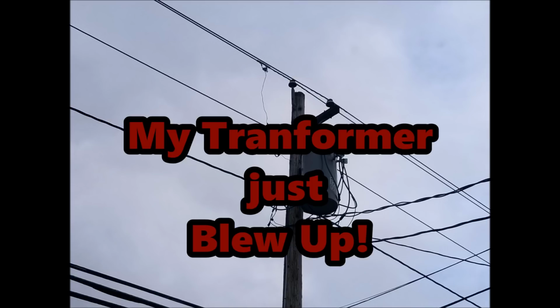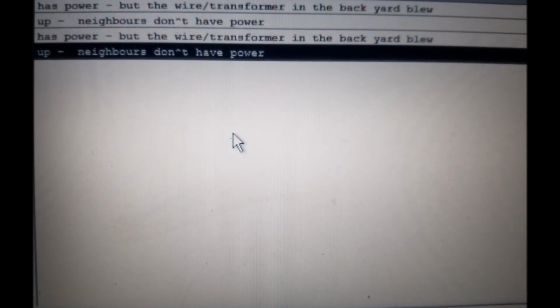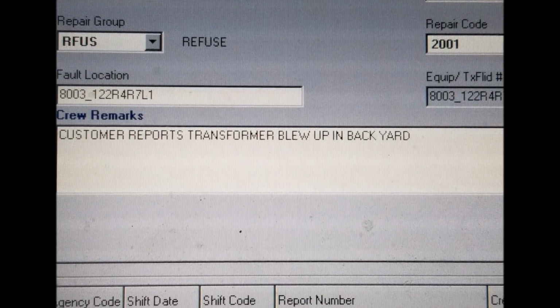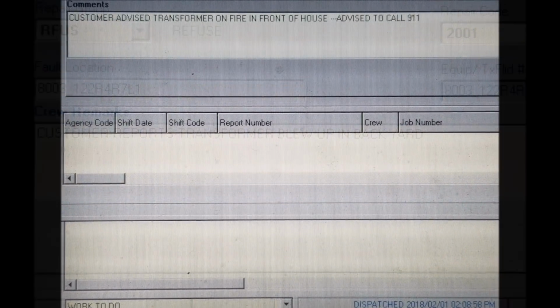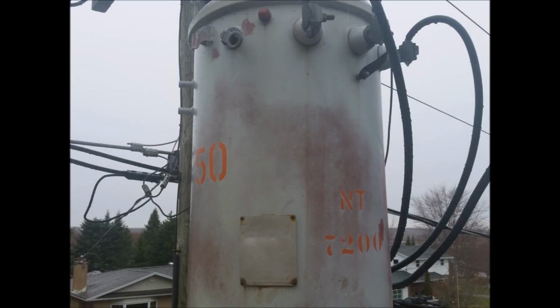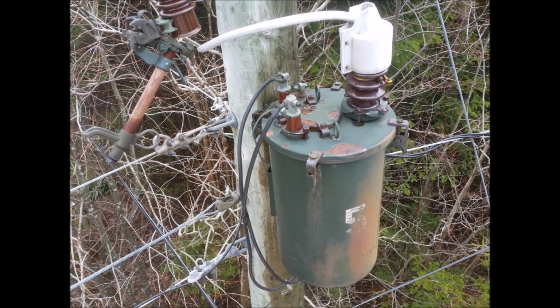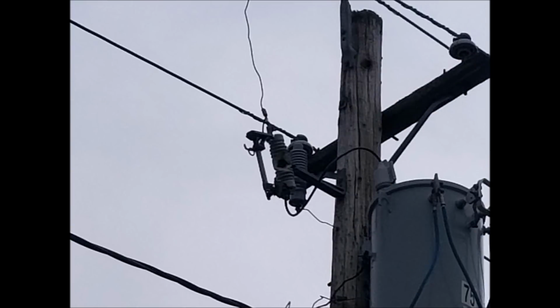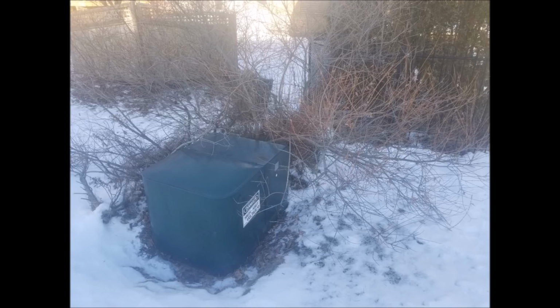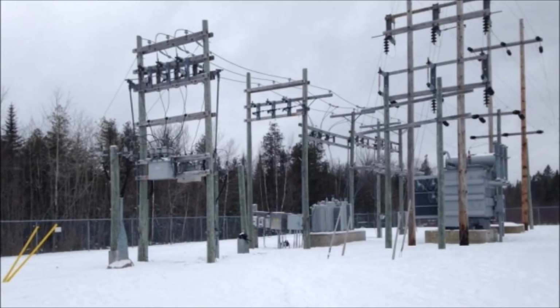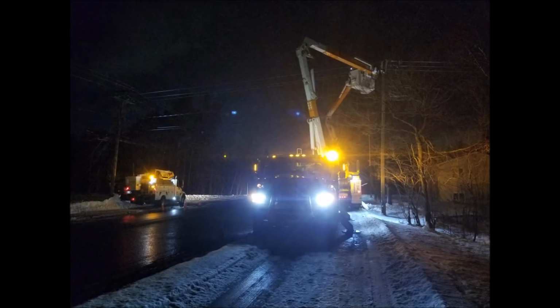Number 1. My transformer just blew up. One of the most common complaints we receive from the public during a power outage is, "The transformer in my backyard just blew up." When, in actuality, this is rarely the case. You see, virtually every transformer that is on the line is protected by a fuse, be it a pole-mounted transformer, a pad-mounted transformer, or a power transformer in a substation. When these fuses blow, it can be extremely loud and is often accompanied by bright flash in various colors that can be seen for miles.